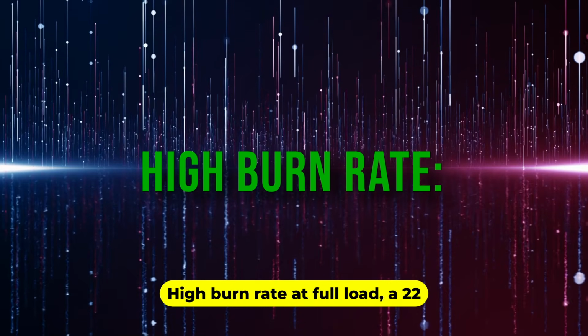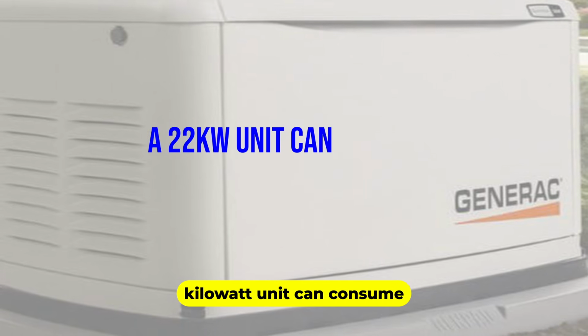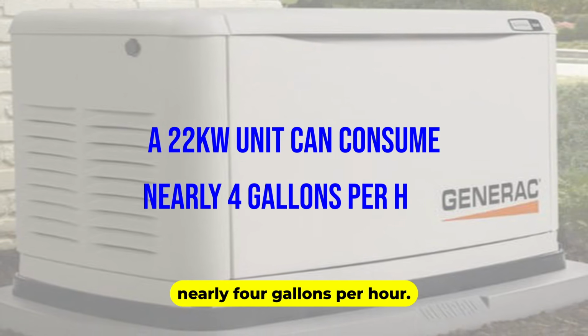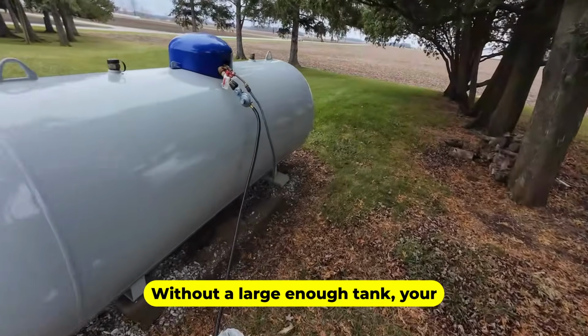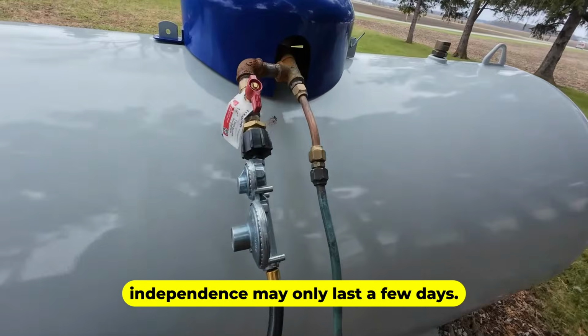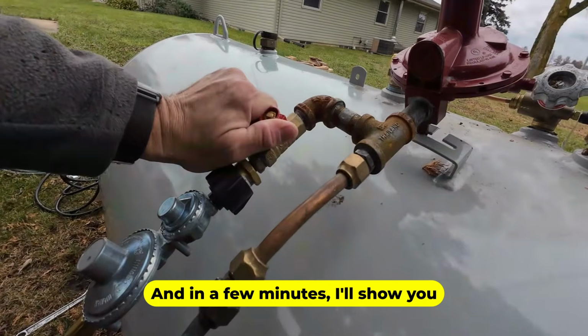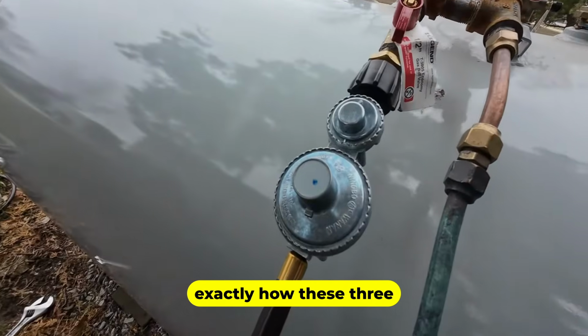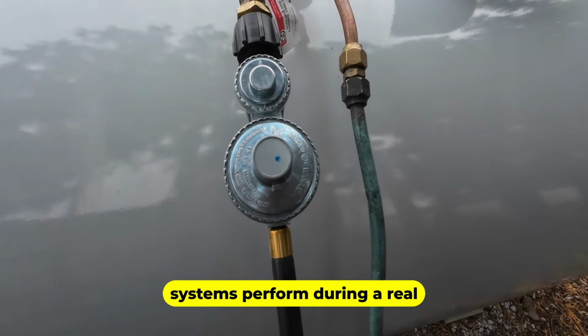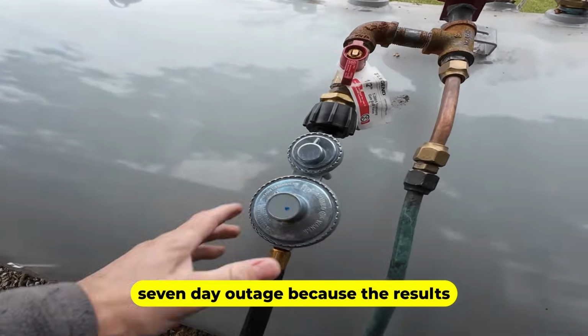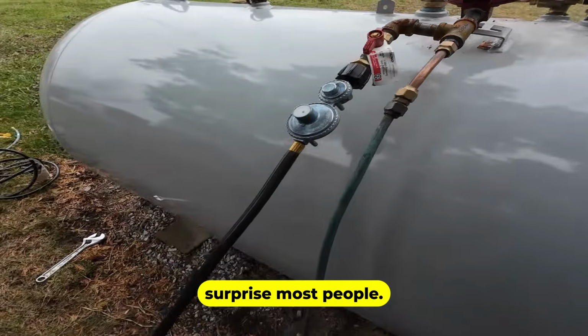High burn rate. At full load, a 22 kilowatt unit can consume nearly 4 gallons per hour. Without a large enough tank, your independence may only last a few days, and in a few minutes, I'll show you exactly how these three systems perform during a real 7-day outage, because the results surprise most people.